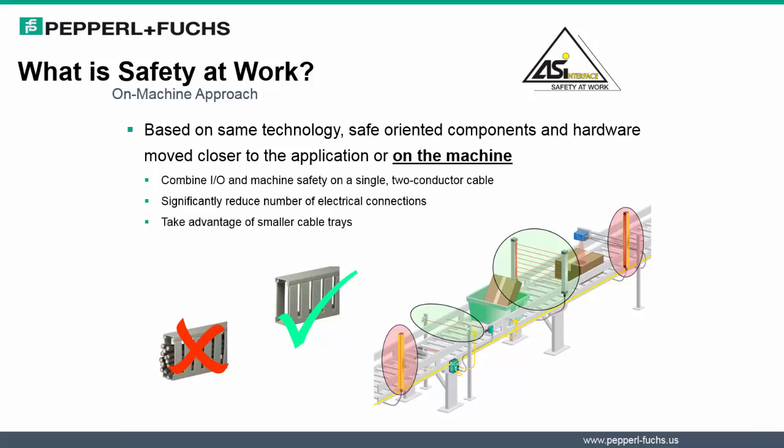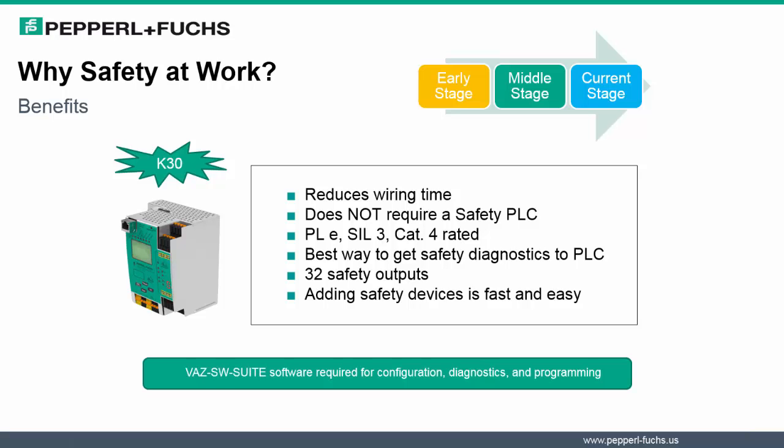Simpler systems result in increased uptime at a lower cost. So, why consider safety at work? There are a number of benefits to highlight. One important one is that safety at work can be added to an existing AS Interface system, as long as the basic AS Interface network rules are satisfied. The evolution did not take place all at one time; I will review the early stage, the middle stage, and the current stage to see how this growth occurred. With safety at work, a safety PLC is not needed, and therefore some costs could be reduced. The highest level of safety is still achievable with SIL 3 and Category 4 with safety at work.